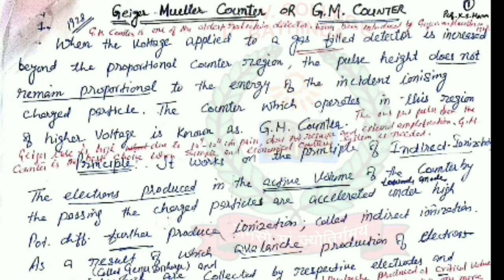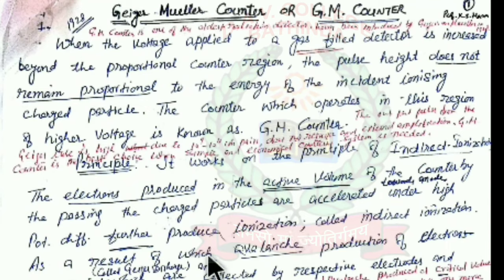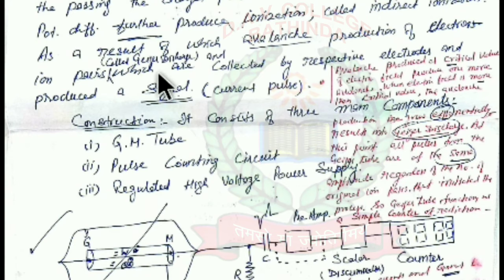The GM counter works on the principle of indirect ionization. Indirect ionization means the electrons produced in the active volume of the counter by a passing charged particle are accelerated under a high potential difference to produce further ionization, termed as secondary and tertiary ionization. The resultant ionization is called indirect ionization, which leads to avalanche production of electron-ion pairs, resulting in a Geiger discharge.